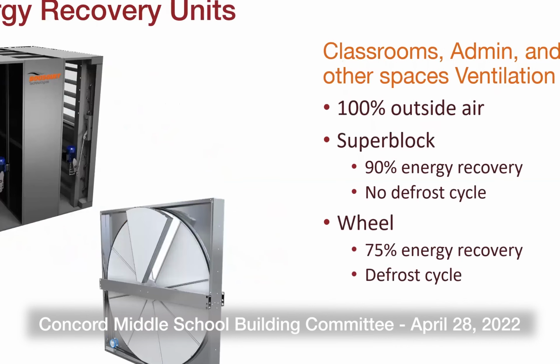Next up, we're going to talk about the energy recovery units. Everything's getting mixed these days, but this is also the DOAS units, or direct outdoor air systems. These will provide 100% outside air to the classrooms, the admin area, and basically all the other spaces that weren't the gym, the cafeteria, and the auditorium.